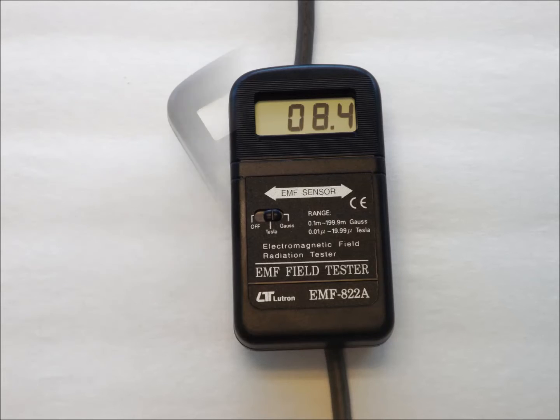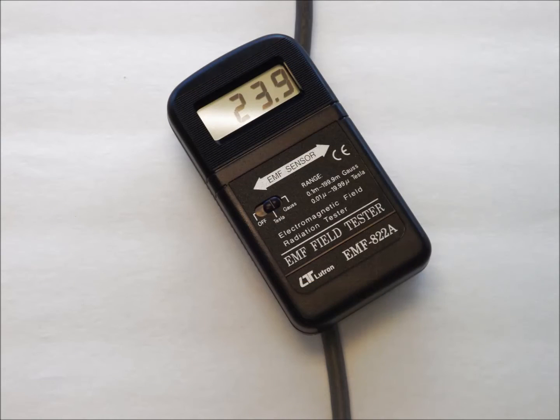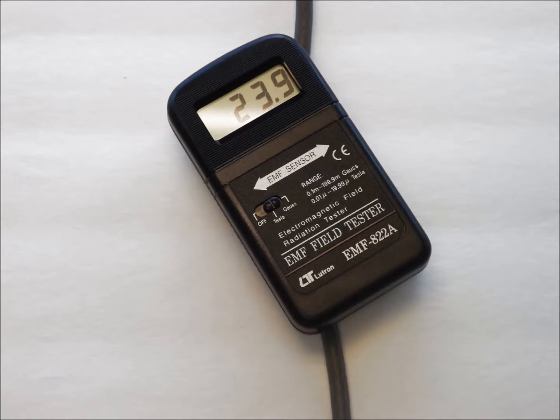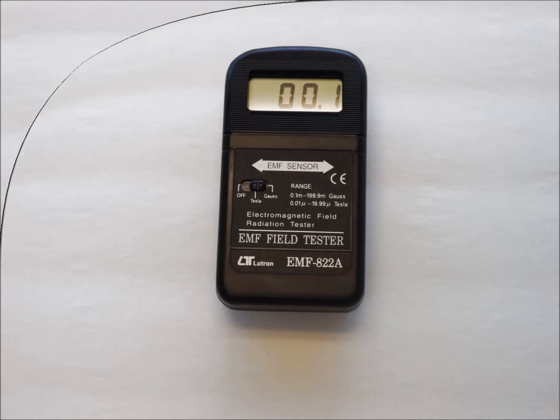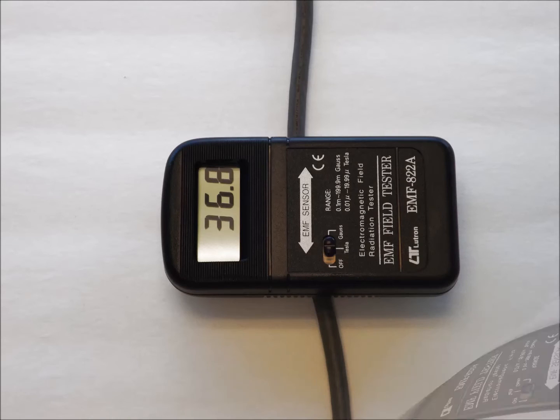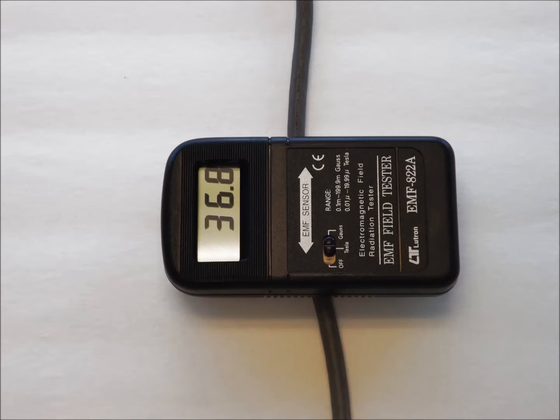One common misunderstanding is that a single axis meter will point towards the source of the field. Not true. Remember, the meter aligns with the direction of the field and the field almost never points toward the source. In the example of the extension cord, the field is perpendicular to the cord.